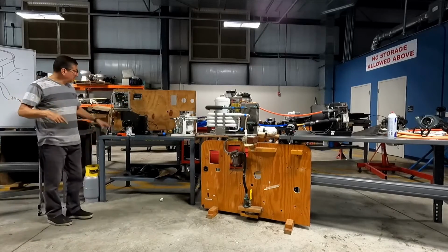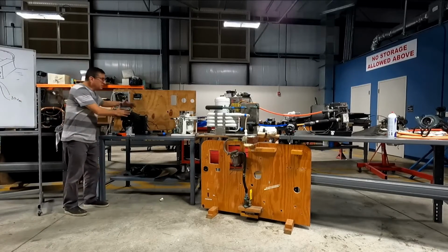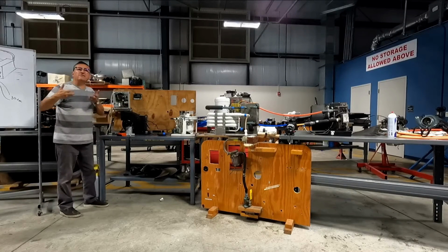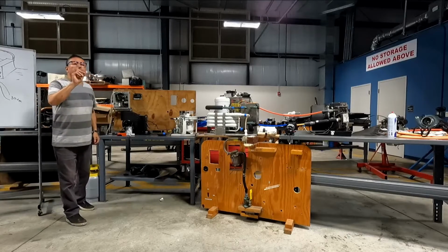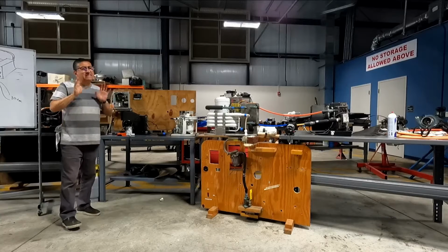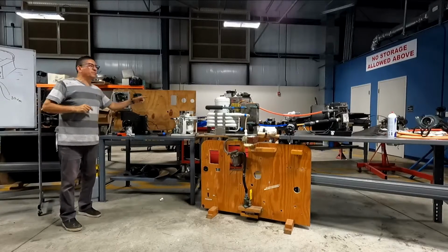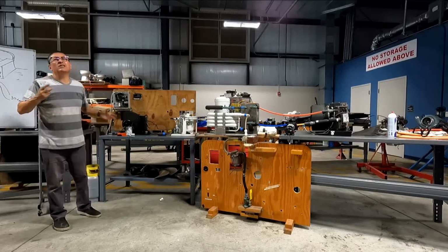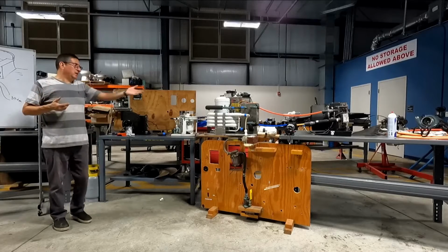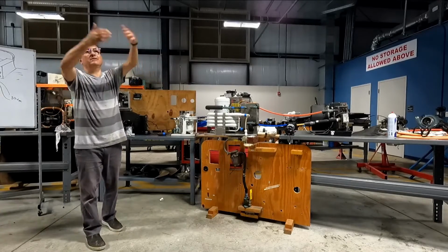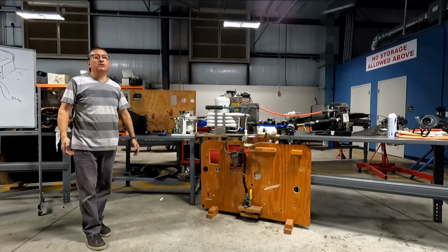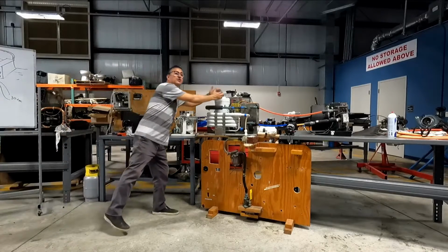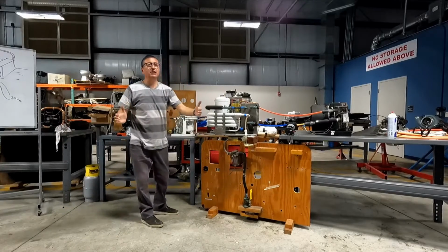Pay attention. We are going to refresh the split unit. In the split unit, the evaporator is located in the cabin, so you would have more than one evaporator per cabin. In a split unit, maximum 2 evaporators per compressor. No more than 2. In this system, you can add 12 air handlers with the same unit. The only limit is the capacity of the central chiller unit.